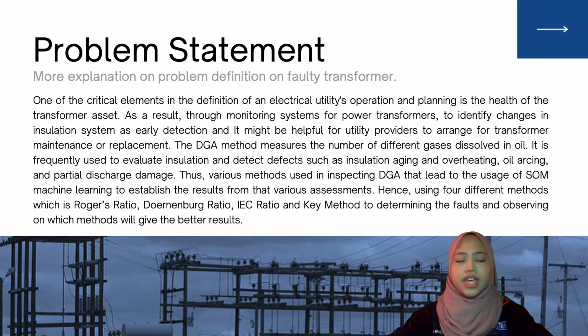Problem statement. One of the critical elements in the definition of an electrical utilities operation and planning is the health of the transformer asset. As a result, through monitoring systems for power transformers to identify changes in insulation system as early detection, it might be helpful for utility providers to arrange for transformer maintenance or replacement. The DGA method measures the number of different gases dissolved in oil. It is frequently used to evaluate insulation and detect defects such as insulation aging and overheating, oil arcing, and partial discharge damage. Thus, various methods are used in inspecting DGA that lead to the usage of machine learning to establish the results from those various assessments. Hence, using 4 different methods, which are Rogers ratio, Doernenburg ratio, IEC ratio, and key gas method, to determine the faults and observe which methods will give the better results.